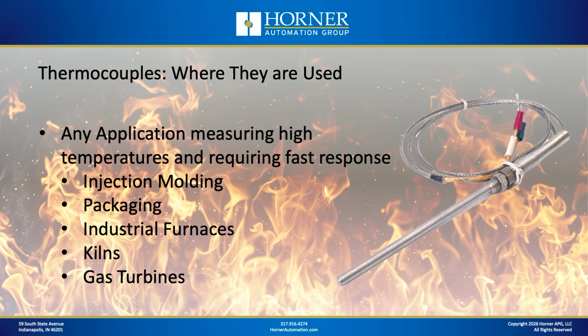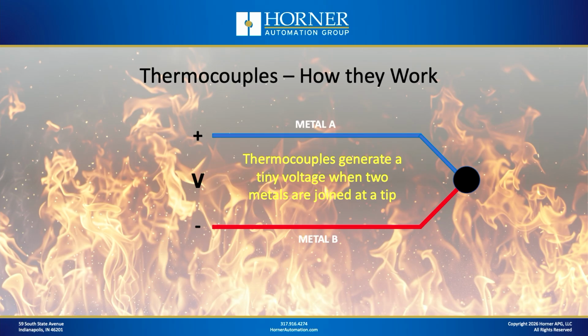Now, where are thermocouples used? Well, again, any application that really needs that high temperature range and that fast response capability, like injection molding and packaging and furnaces and other applications like that, will use thermocouples because that's really the best temperature sensor for those applications. Now let's talk about how thermocouples work. That's where we get into the little bit of the voodoo here. One thing that's interesting, at least I always have thought it's interesting, is that the thermocouple effect is something that happens when you take two differing metals and you join them at a tip. What happens is a tiny voltage is generated at the tip, and we are talking a pretty tiny voltage.